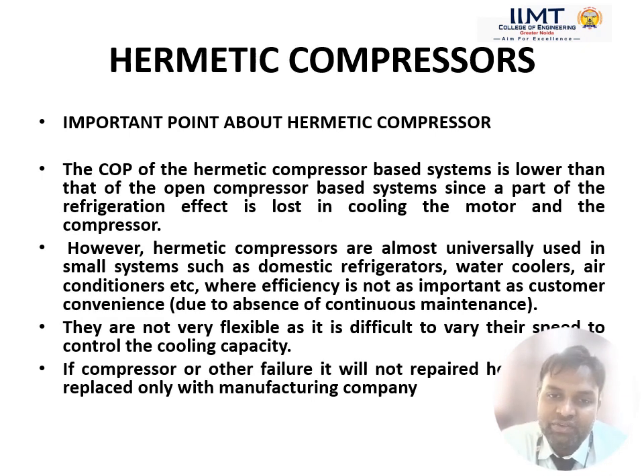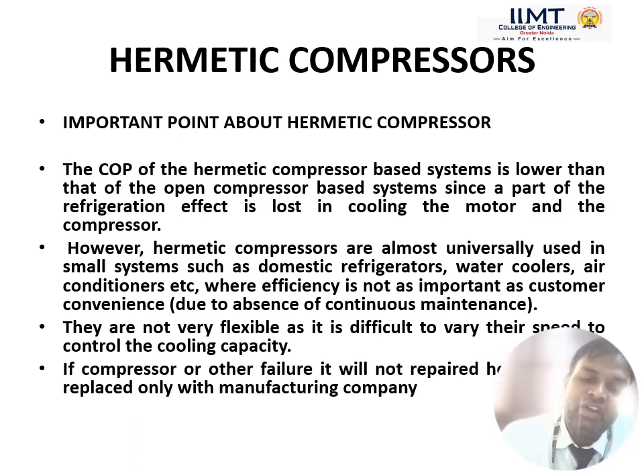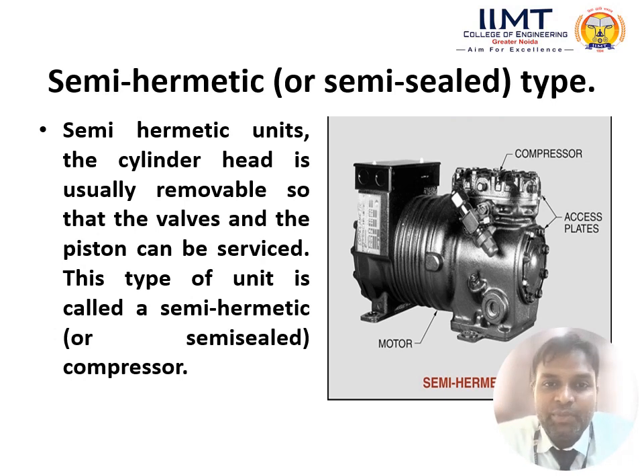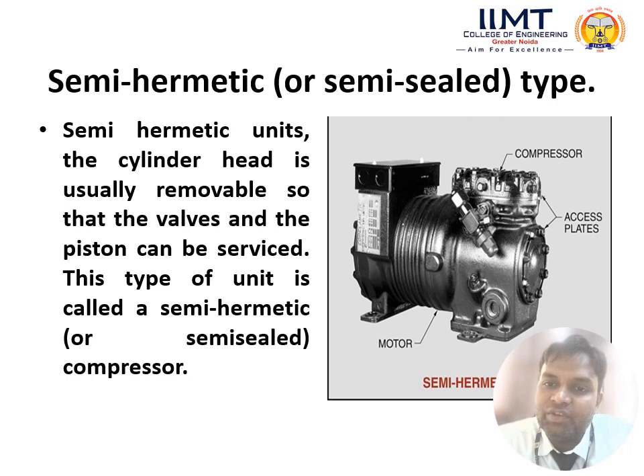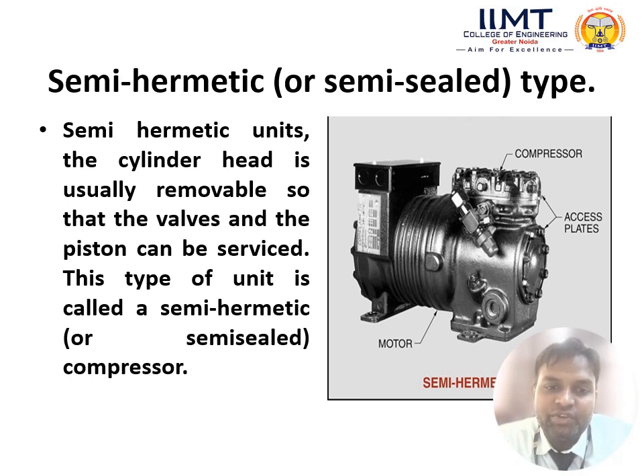Hermetical compressors are not very flexible as it is difficult to vary their speed to control the cooling capacity. Also, if the compressor fails, it cannot be repaired at home — replacement is the only option since the whole compressor unit must be replaced. In the semi-hermetical or semi-sealed compressor, the valve and piston can be serviced as the head and cylinder are accessible from outside the enclosure.